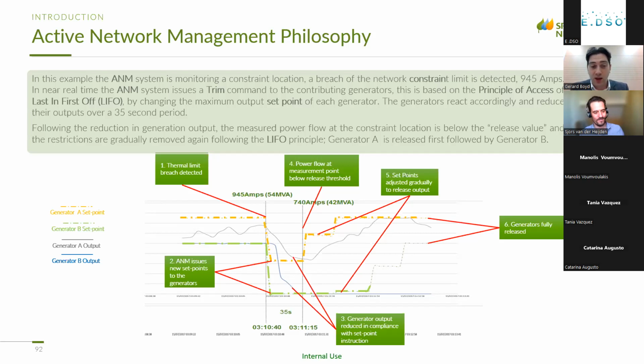Generators in that area could be connected under ANM, or under a full firm connection from a historic connection. We have upstream monitoring points feeding into a system that looks at load flow analysis, power systems analysis, and network topology to identify, at the constraint points, what the set points need to be in real time.